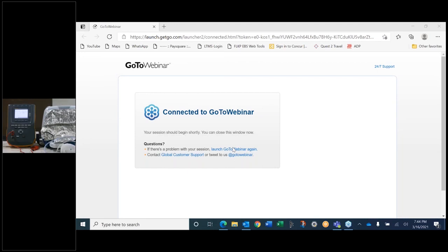Okay. Next, actually, we don't do mains and applied parts or anything because a ventilator doesn't have applied parts. This is to be noted. There will not be any mains and applied part test for a ventilator. Okay.